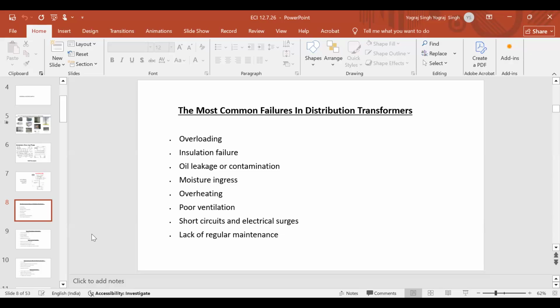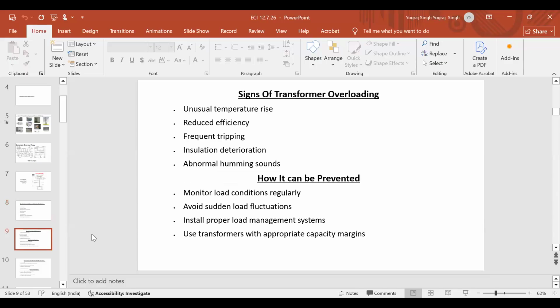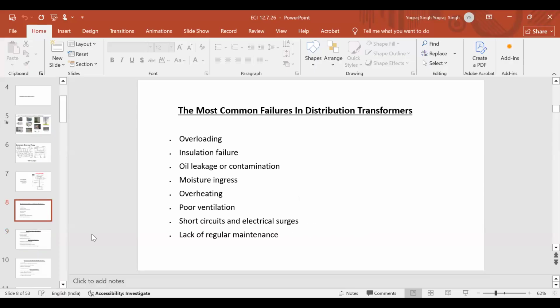Now you have to imagine a three-phase transformer as a combination of three single-phase transformers. Suppose one phase is overloaded by 100%. This transformer can burn anytime while the other two phases are intact. Then next is insulation failure. Most commonly, the transformers used are oil filled. Insulation failure will occur when there is moisture inside it or there are carbon particles inside the tank. Now what will happen? It will increase the conductivity of the medium. Normally this oil has better dielectric strength, around 50 kV per centimeter. So if that dielectric strength is maintained, nothing will happen, no short circuit, nothing.